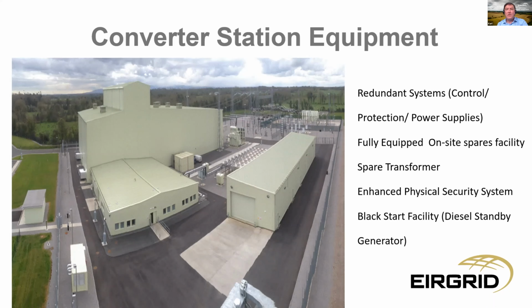The asset is designated critical infrastructure under NIS-D, the Directive on Security of Network and Information Systems. In addition to a number of cybersecurity initiatives, we have made investments to enhance physical security on site. That's the physical security perimeter fence that we have. The East-West Interconnector is a voltage source converter which can independently control active and reactive power. With such technologies, a voltage reference can be applied to a black network with the support of a standby diesel generator. The black start functionality is provided to both EirGrid and National Grid ESO, and the diesel generator is located here.